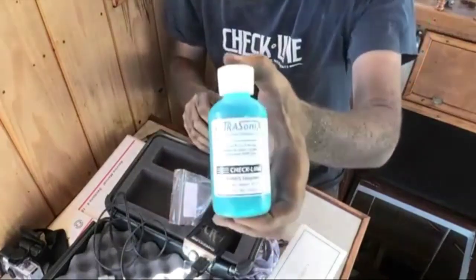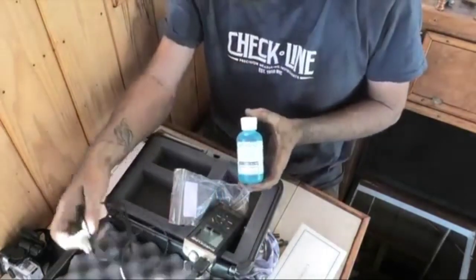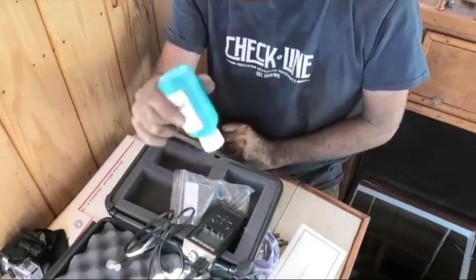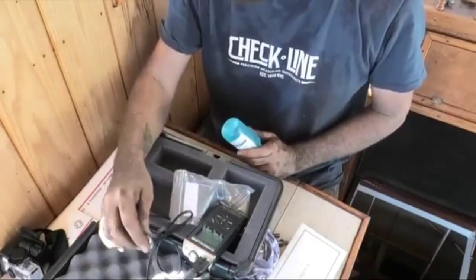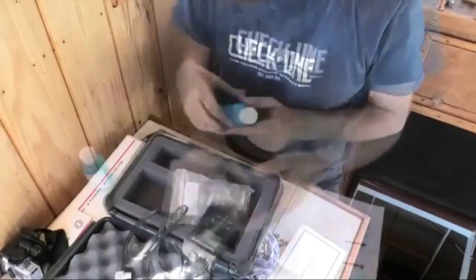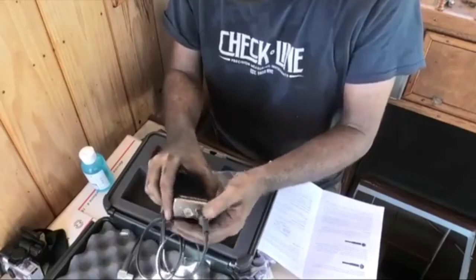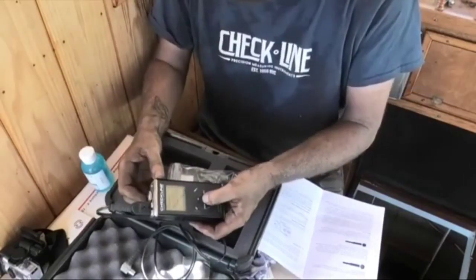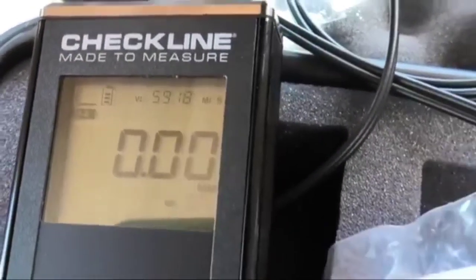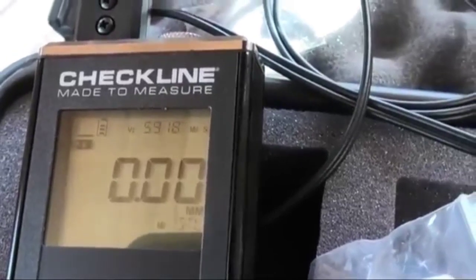Then you get a little bit of the coupling solution. You can't have an air gap between the transducer and the metal, so you put a few drops of the coupling solution onto the metal, then you can press the transducer onto it and know you've got a good connection. It's powered by a couple of AA batteries that live under here. So switch it on.